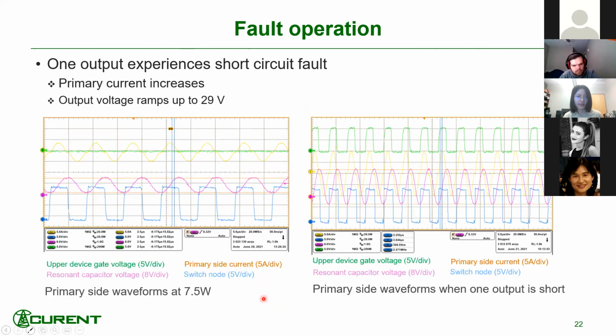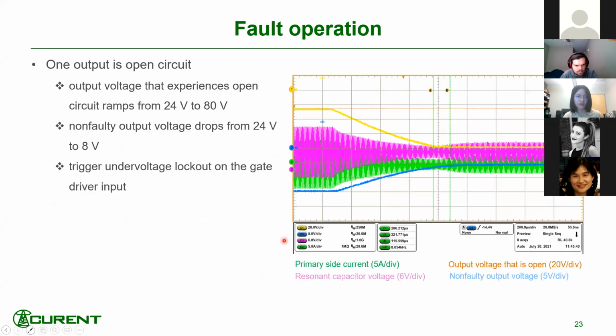And this is the waveform in a short circuit fault. So as you can see, even though the waveforms are still sinusoidal, the current increases a lot and the output voltage just ramps up. And here is the open circuit fault. The voltage ramps up and the non-faulty output voltage drops. But this is kind of detrimental to the gate driver because the gate driver always wants a stable voltage input.